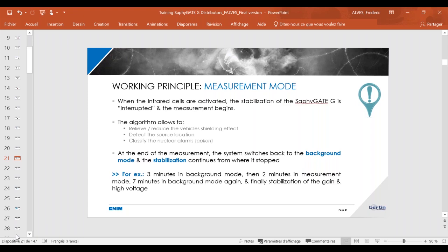Then, at the end of the measurement, the system switches back to the background mode, and the stabilization continues from where it stopped. So it means, for example, that if you have first 3 minutes in background mode and then 2 minutes of measurement, you will come back to the background mode again during 7 minutes in order to have the stabilization of the gain and high voltage. Okay.